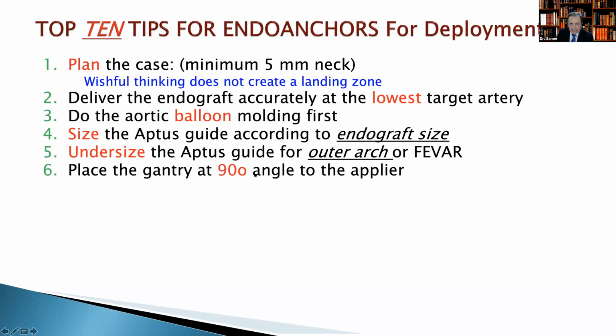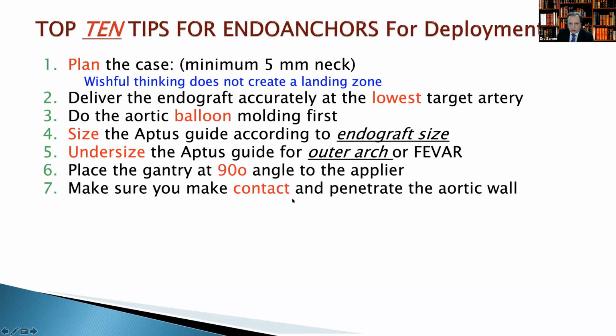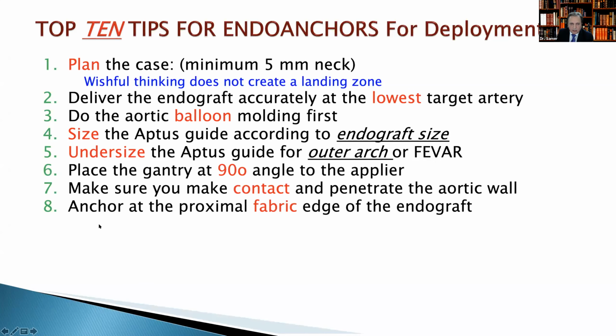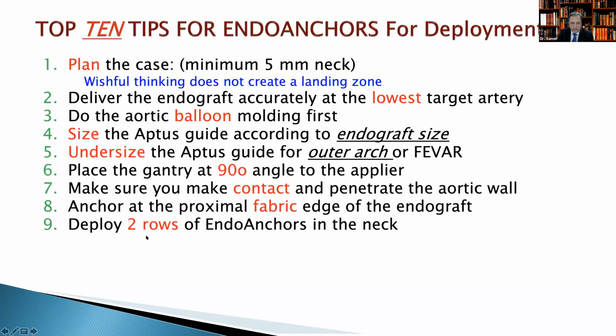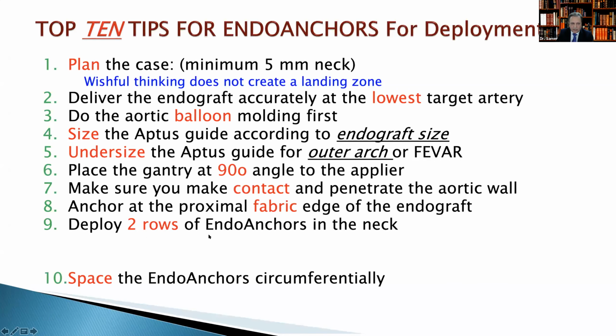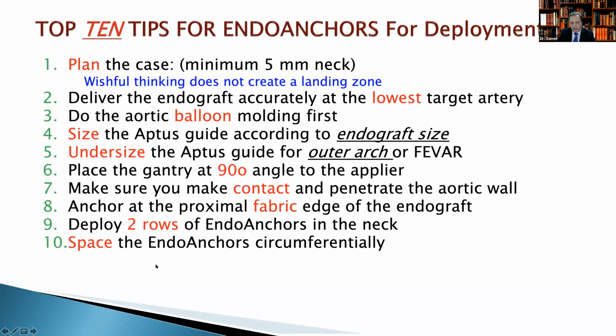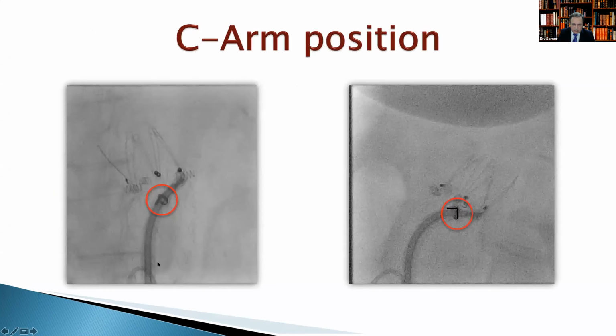Always place the cantilever at 90-degree angulation. Make sure you contact and penetrate the aortic wall. You need to anchor the proximal fabric very close to the edge, so you have to put your anchors very close to the edge of the fabric of the EVAR. And finally, if you can deploy, it's better to put 2 rows if you can. And finally, try to space the endo anchors circumferentially so you get a good seal, not only in the area where you have a concern.